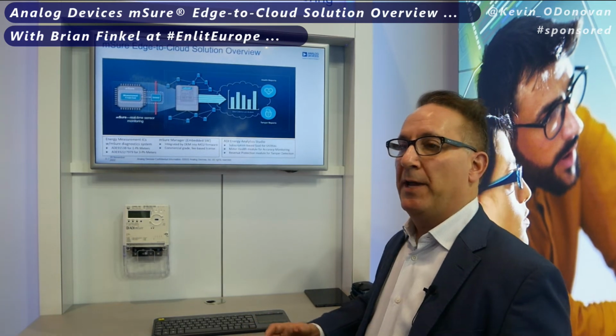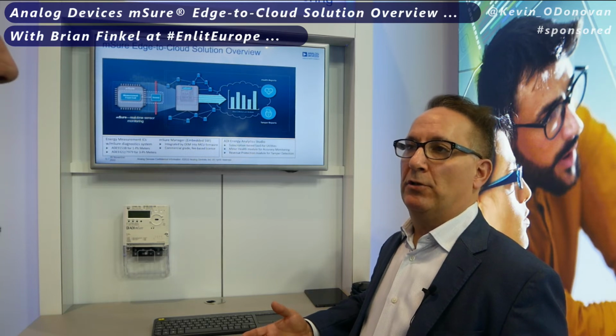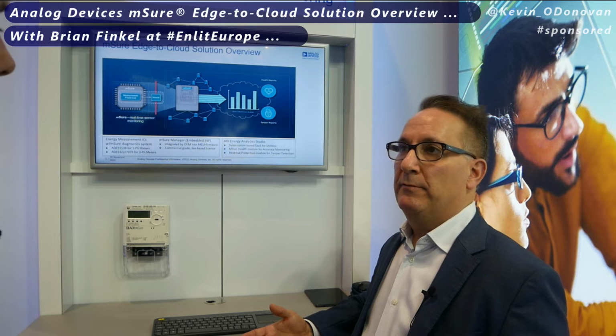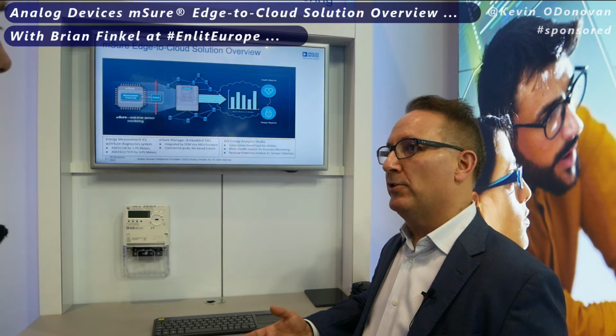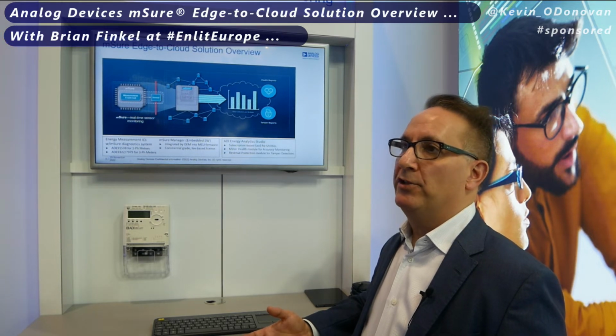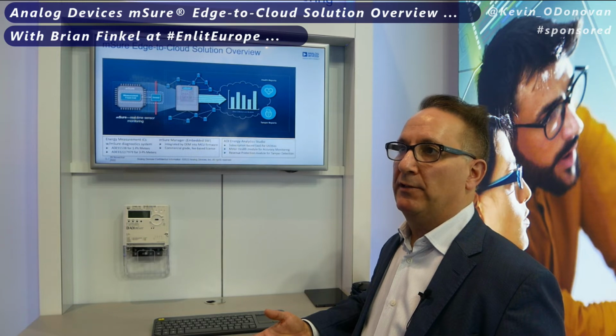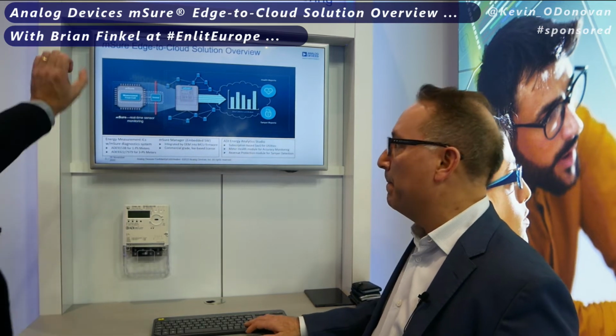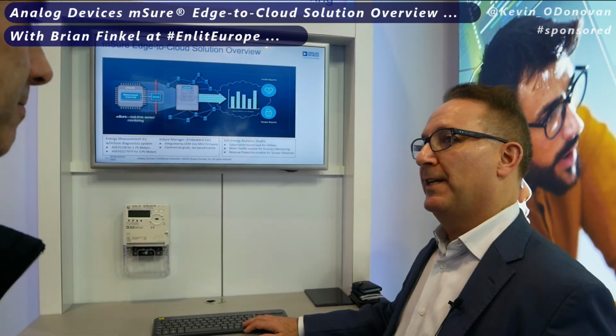The way it works is Analog Devices has an energy metering IC, and we've been selling energy metering ICs for over 15 years. And our latest generation has a new feature called the mSure diagnostic system. It's on the chip. It continuously monitors the current and the voltage sensors for any changes since the initial calibration of the meter. Okay? That data that's generated by the diagnostic system is then sent over the utility network to an analytics service, which then processes the data and produces the insights for utilities. It's a set of insights on meter health or meter accuracy, and there's a set of insights on meter tampering, or what we call revenue protection. Okay? So you're inside the chip, in the meter, edge to the cloud. That's correct, yes.